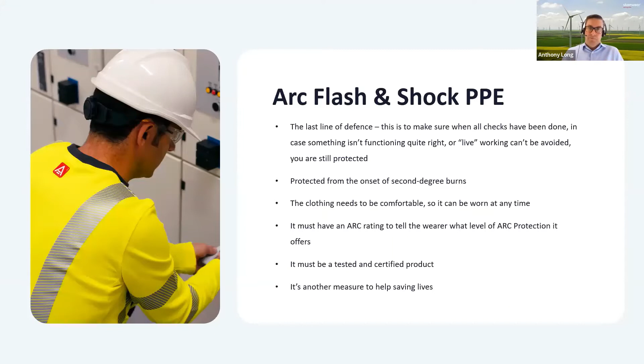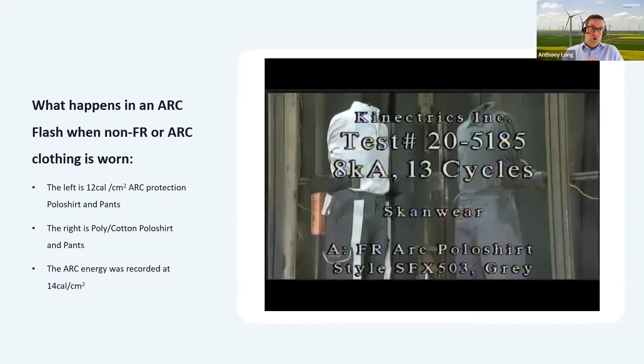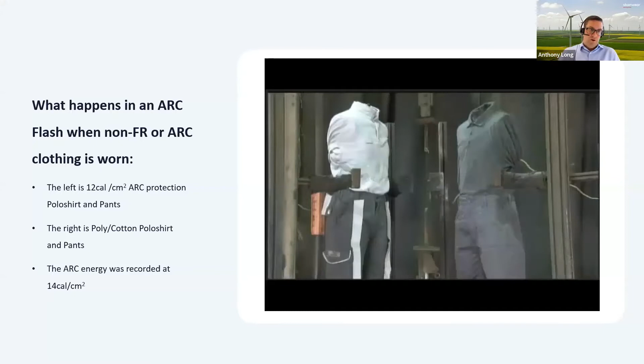So this was a video I talked about before of why you would wear arc flash PPE or not wear arc flash PPE. You may have a situation where you think, I don't need arc flash PPE, I'll just wear some general PPE. We've talked about human error. We've talked about systems where the equipment might be faulty. It might arc on its own accord without any human interference, but you might be in that vicinity. When you're not wearing arc flash clothing, you'll see from this video now what happens in that situation. On the left-hand side, the light grey top and dark grey pants are 12 cal arc protection. On the right is a polycotton polo shirt and pants.